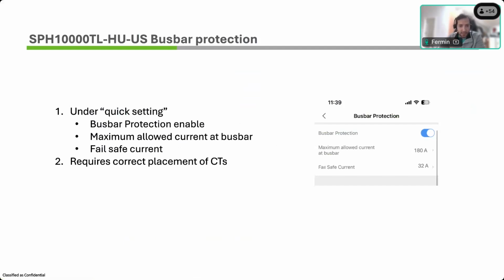using the PCS function. It continuously monitors the current from the CTs coming from the utility, or the power coming from the utility, and the power being output by the inverter, and it allows you to control the output of the inverter to make sure that the rating of the busbar never gets exceeded.